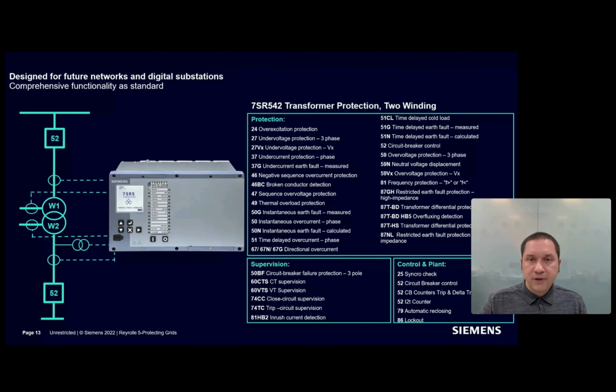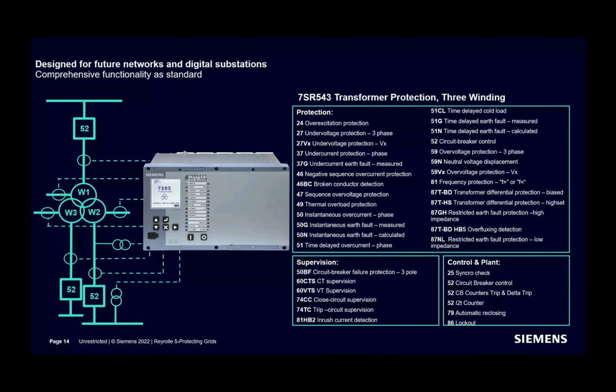7SR542 is available in 2 case forms, size 8 and size 12. Now, coming to the 3 winding version, 7SR543 is our 3 winding version. Again, it is available to choose a CT only version or CT and VT version, depending on the requirement. It has 12 CT inputs, which are suitable for connection to both 1 amp and 5 amp again.